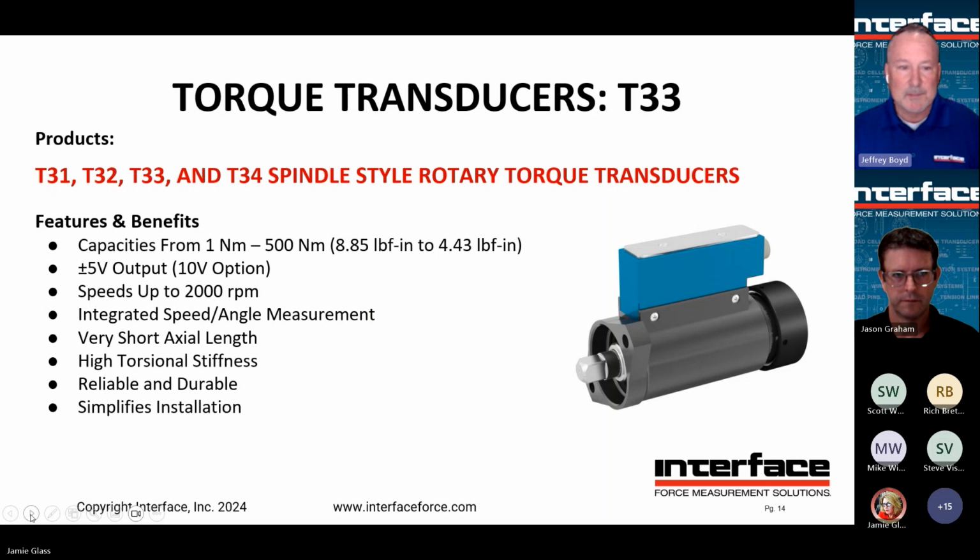The T33 spindle torque transducer. So this again is a rotating torque sensor. High level analog outputs, ±5 or 10. Can have integrated speed and angle measurement. So if torque and speed needs to be maintained or controlled within specific limits, you can do that with this type of device. You can monitor torque levels, make sure that your machine is running and operating as efficiently as possible by integrating this into some type of torque control loop feedback.